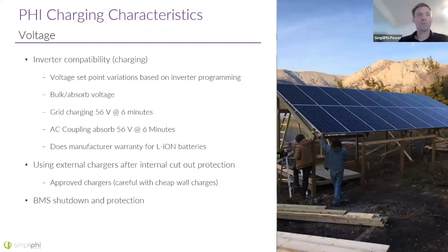Okay, so on charging characteristics of the PHI batteries, we need to make sure that we're using compatible charging equipment. Now, most modern equipment is designed for charging lithium batteries, but if you're using older equipment, make sure that the set points are able to be properly set for lithium batteries, and specifically for our lithium batteries. So if you don't have the ability to control the bulk and absorb voltage, do not use that charging equipment. Right? You need to be using equipment where you can program the appropriate settings in.